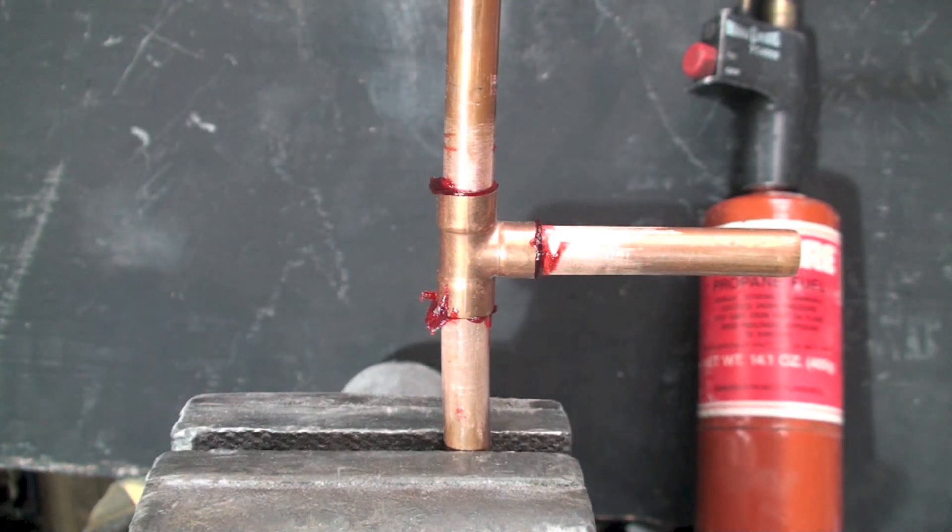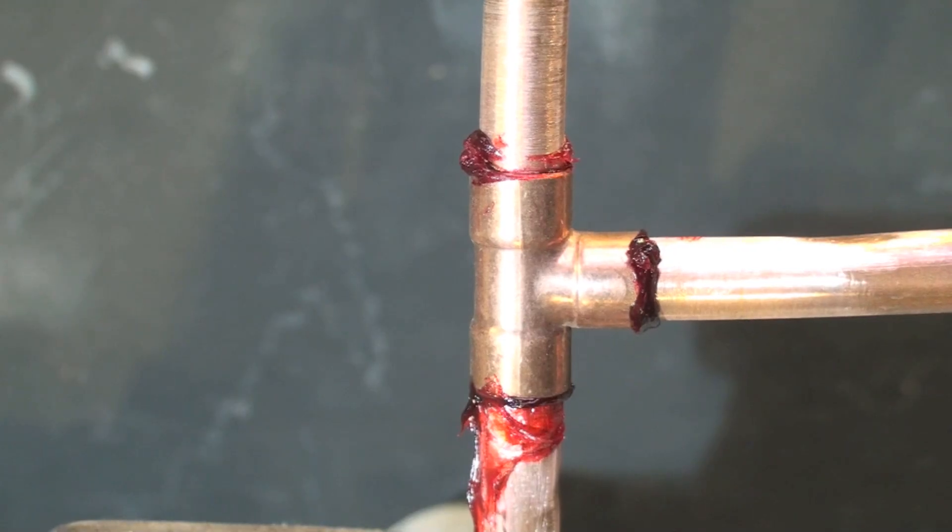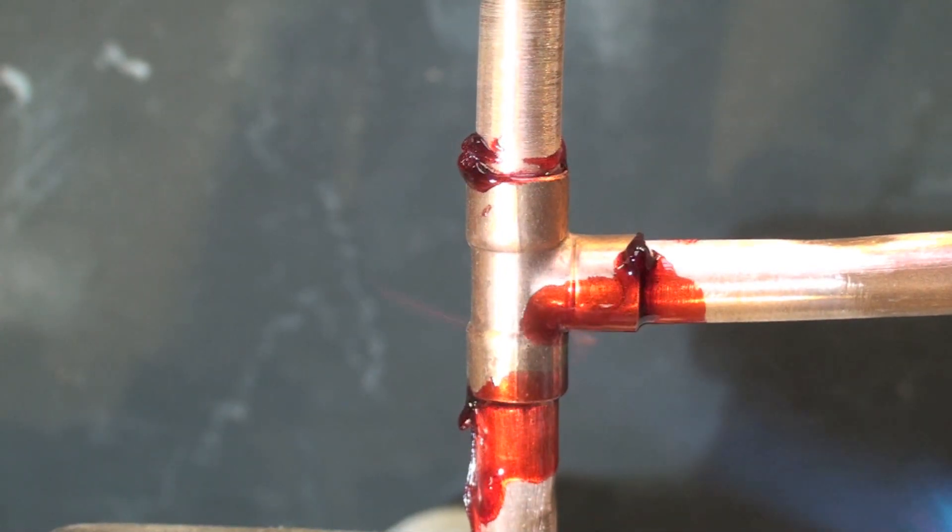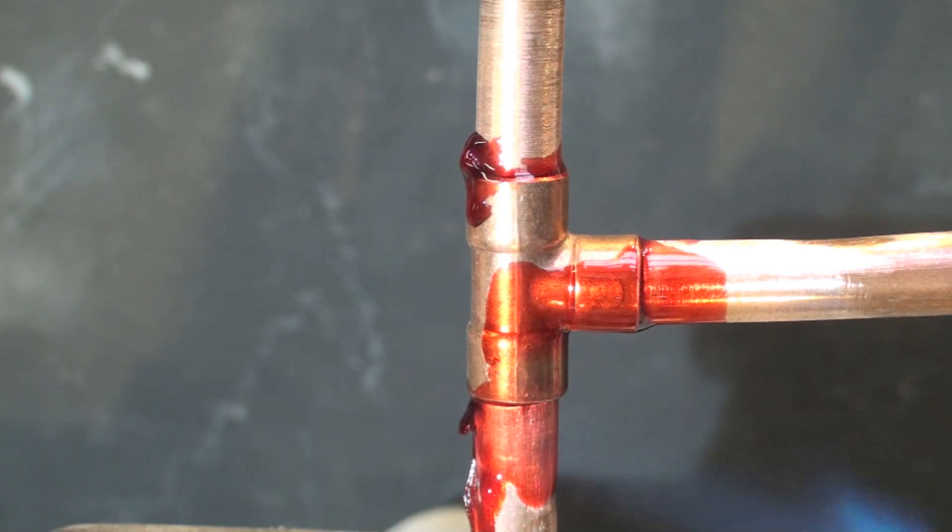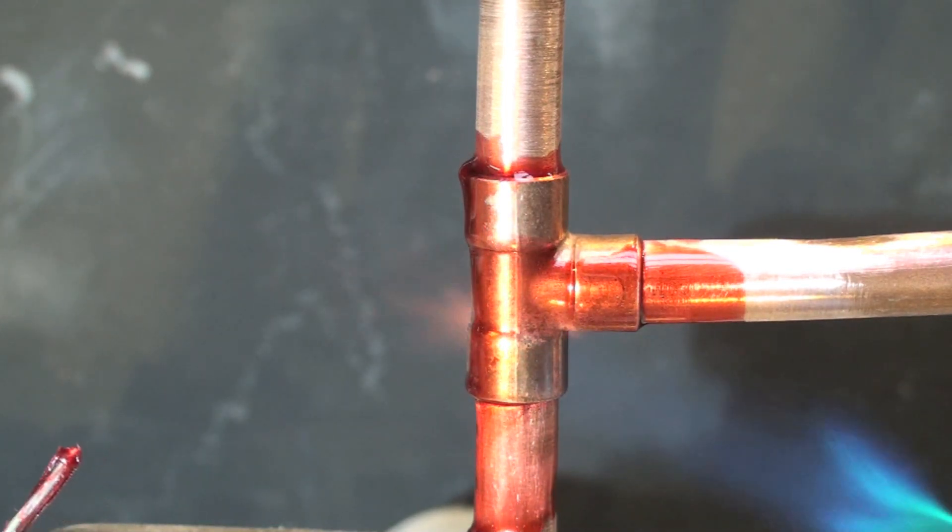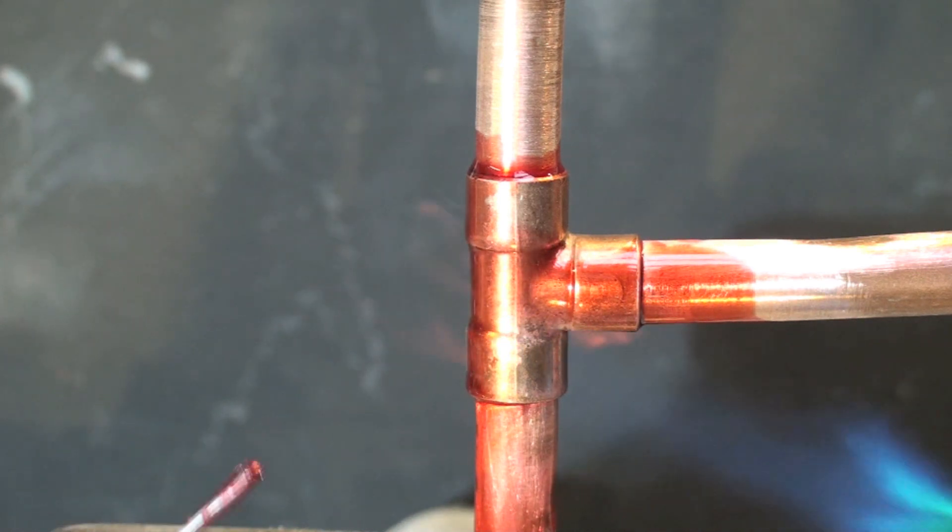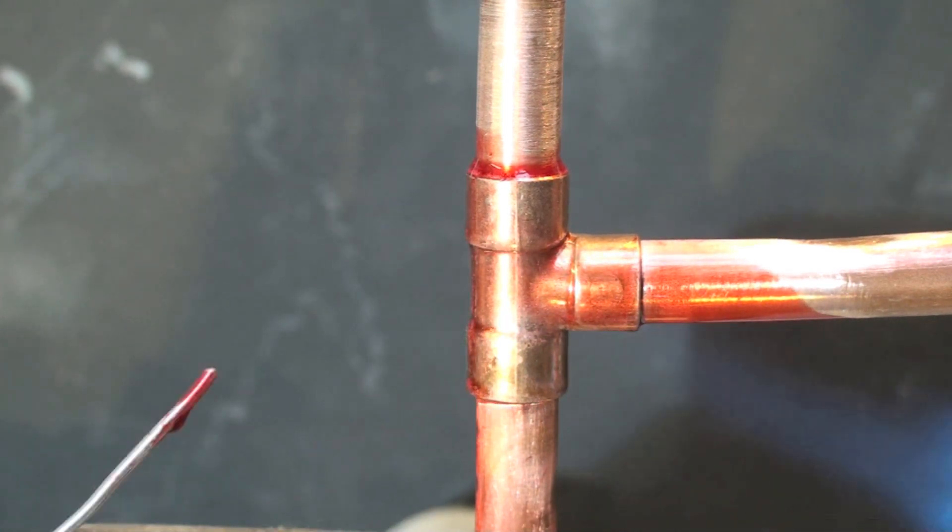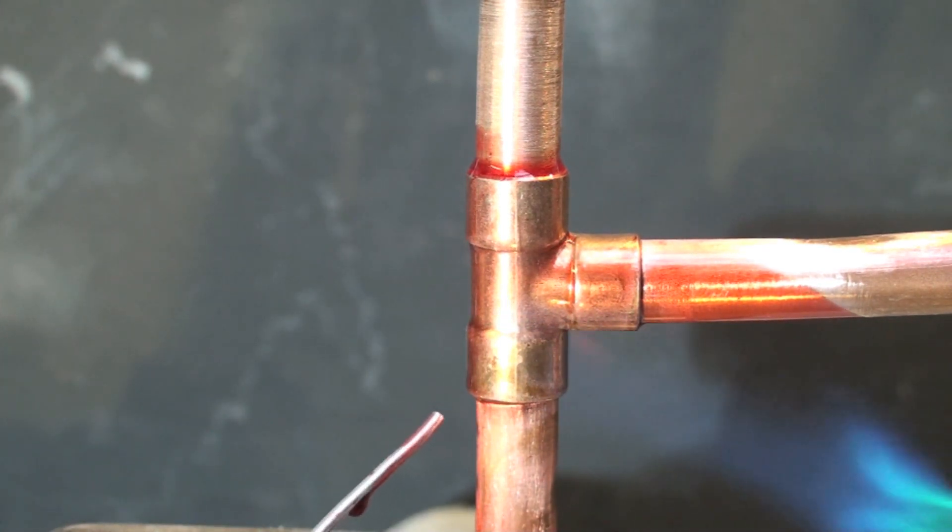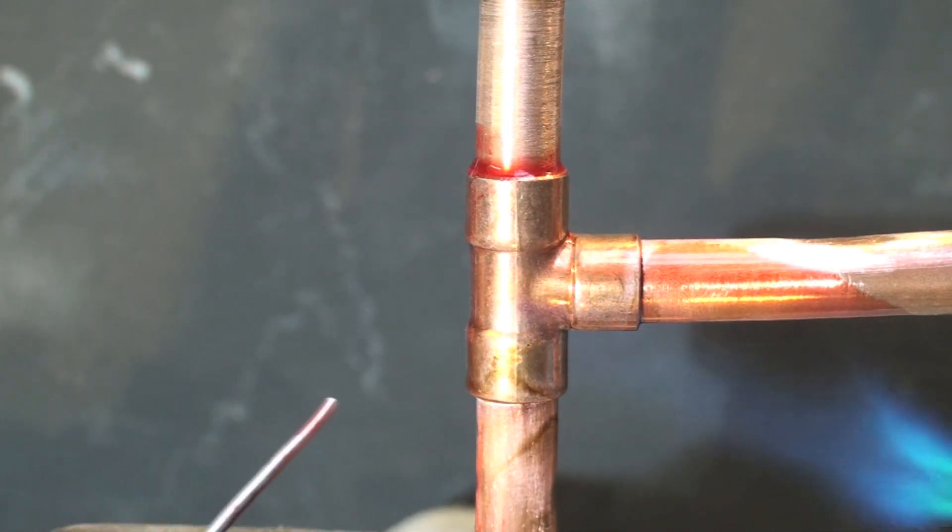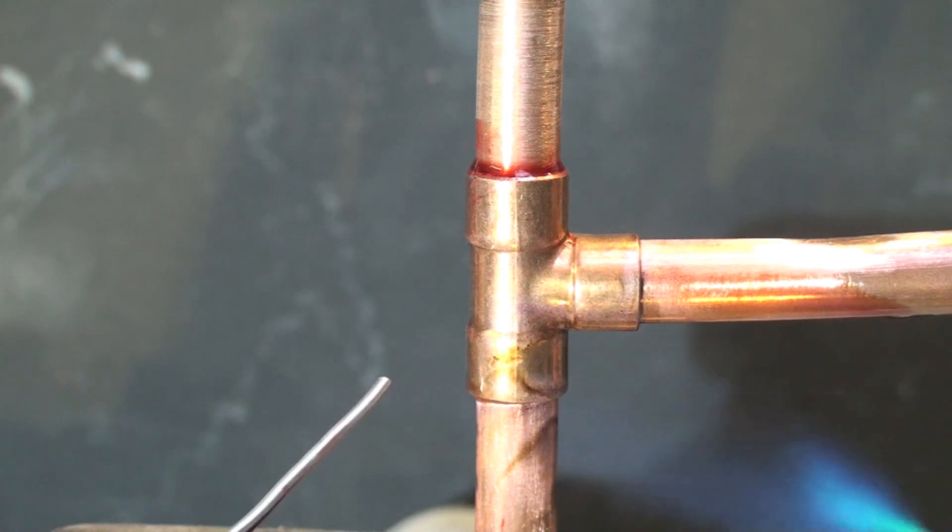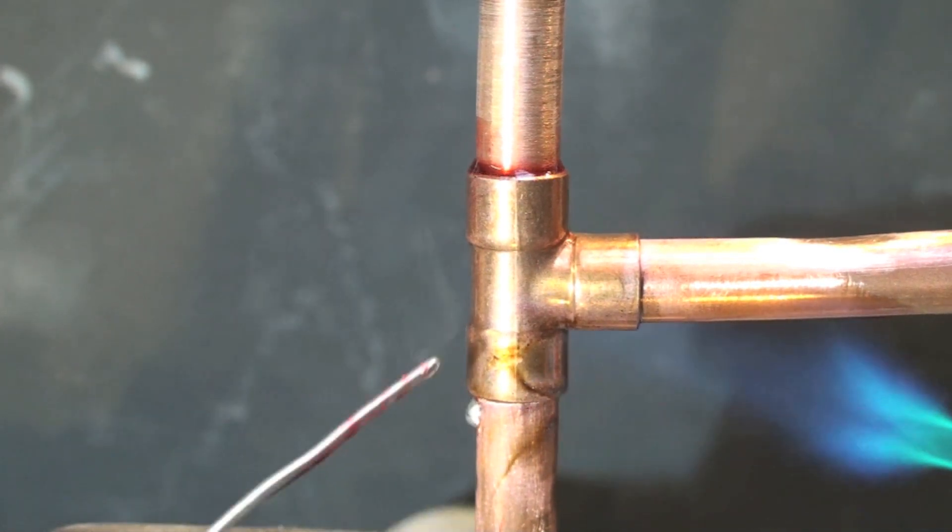Here we're going to start heating this thing up. You can see the flame is melting the flux. You're trying to control this - you're doing the bottom one first and you're on the female side to heat up there, and it's going to heat up the other pipe. You're touching on the opposite side with the solder material, waiting until it will actually suck up. It actually sucks up pretty fast - like right there it's pretty much sucked up in here.